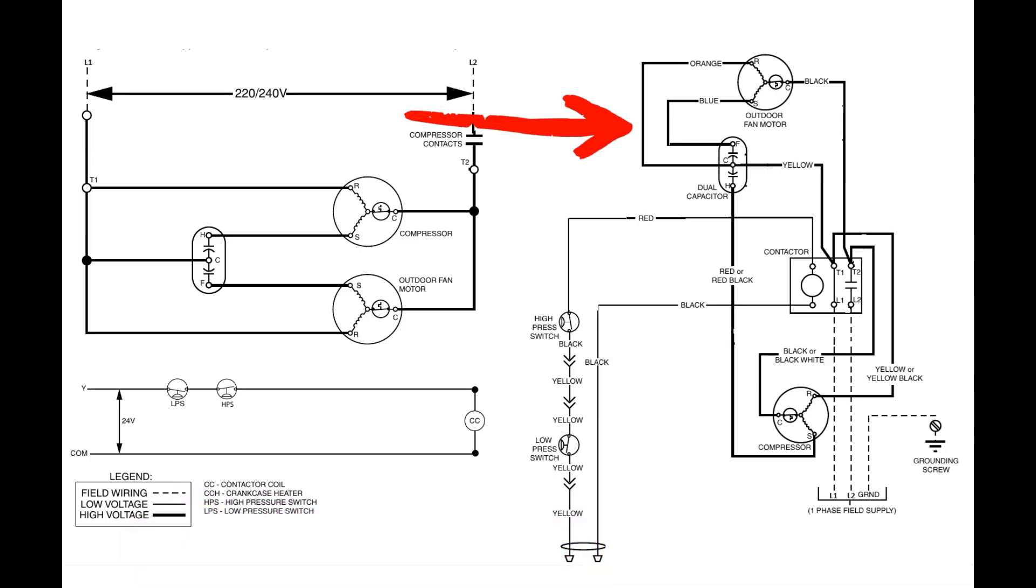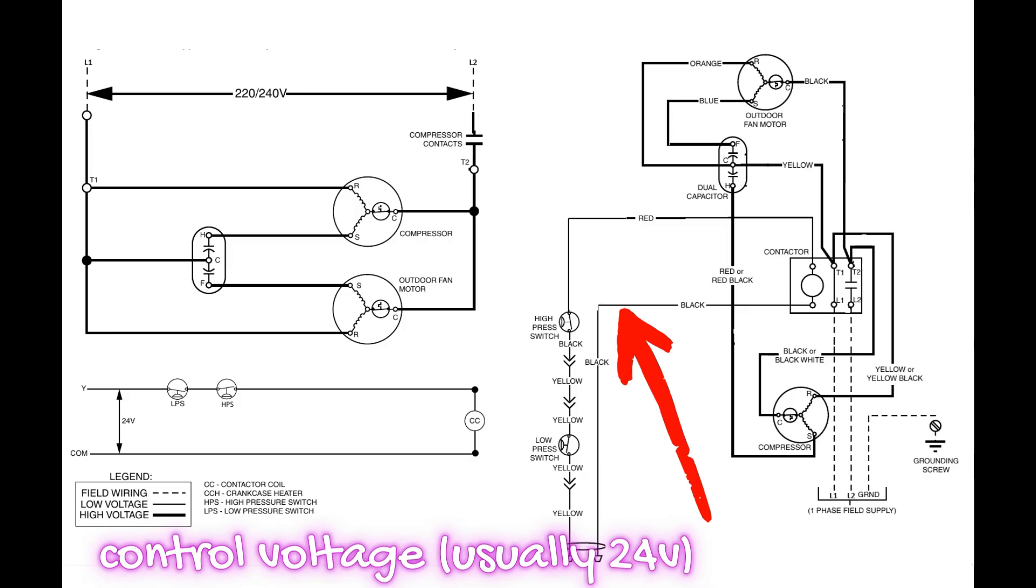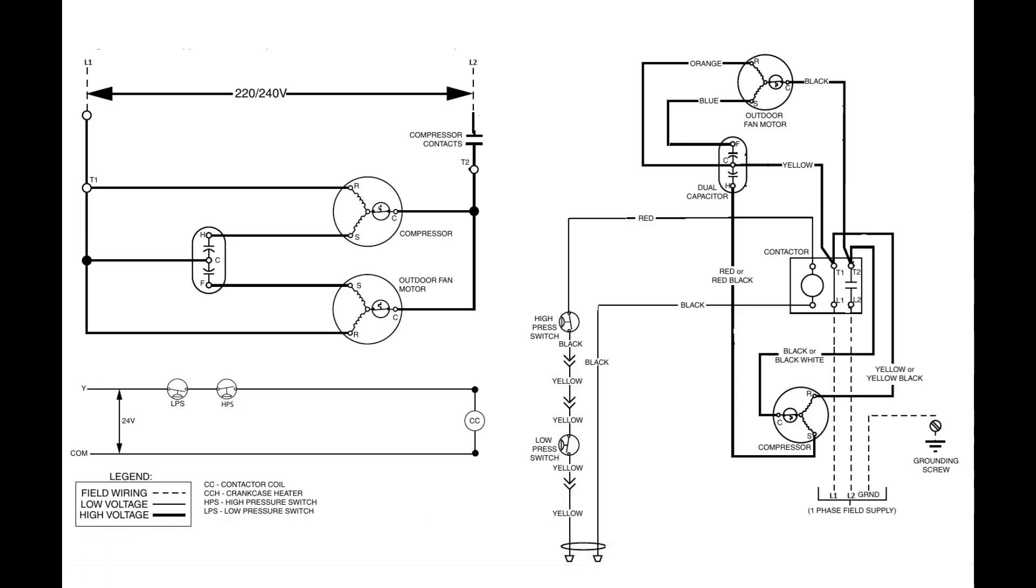When we see thick black lines, what we're looking at are high voltage lines. This is the power we need to run the heavier pieces of equipment, compressors, fan motors, circulator pumps, and things of that nature. The thin black lines are what we call control voltage. This is usually 24 volts.